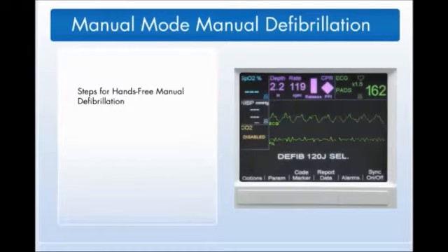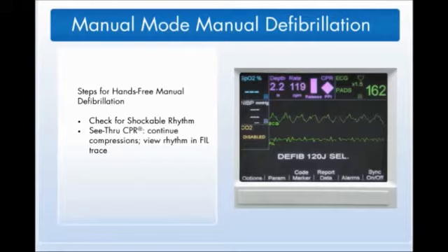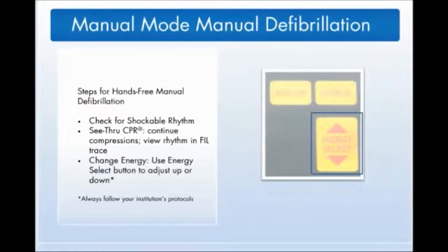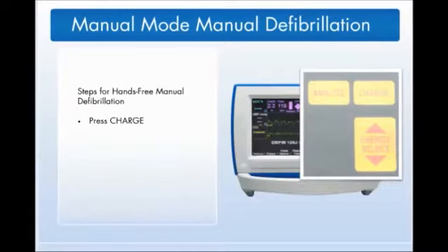Check the display monitor and verify the presence of a shockable rhythm. If you are using the R-Series with see-through CPR, continue compressions and verify suspected rhythm using the filtered ECG waveform on the monitor. If desired, ALS providers can change the default energy setting by pressing the Energy Select button up or down. Press the Charge button.